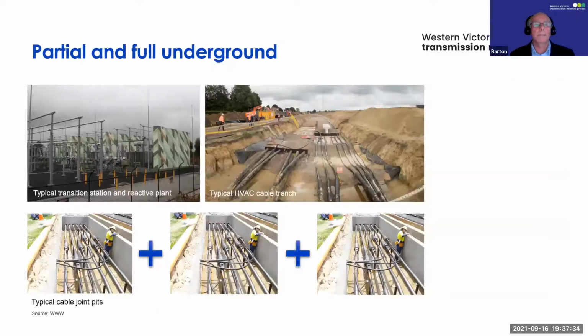More photos - if it goes to partial undergrounding, because of losses on cables, there needs to be reactive plant or transformers about every 25 kilometres, as shown in the photo top left, to boost the voltage and ensure losses across the entire transmission circuit are manageable and within the needs of the system.